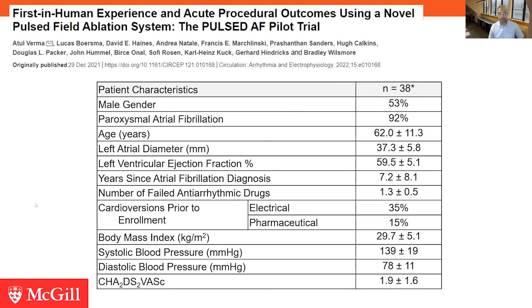In terms of the system being evaluated, this is the Medtronic PulseSelect pulsed field ablation system. As you can see by this picture here, it is a circular shaped catheter with 9 gold electrodes. And you may perhaps recognize this from the old PVAC days, but the catheter was refurbished and redesigned in order to be able to deliver pulsed field ablation. In terms of the waveform, these are bipolar deliveries using biphasic pulses.